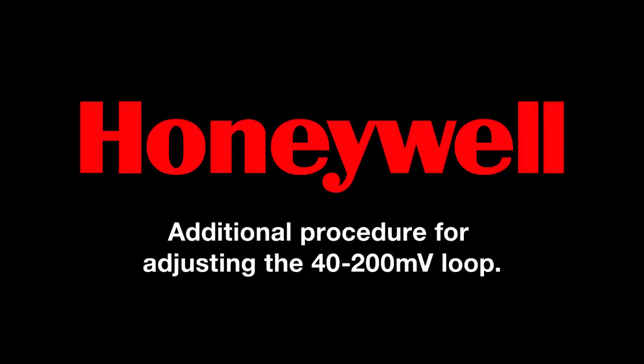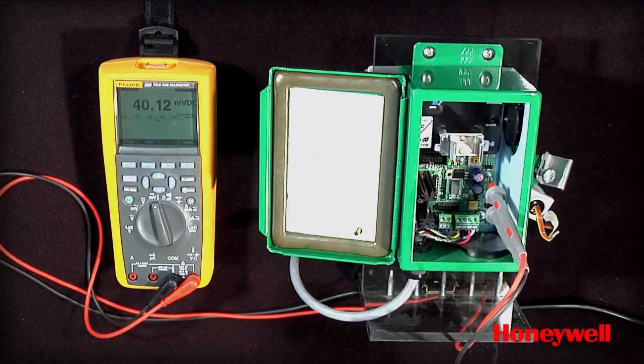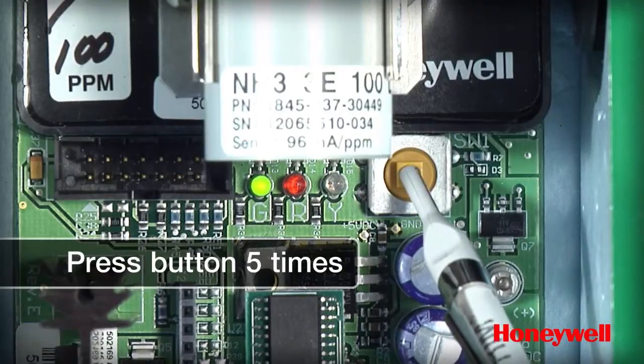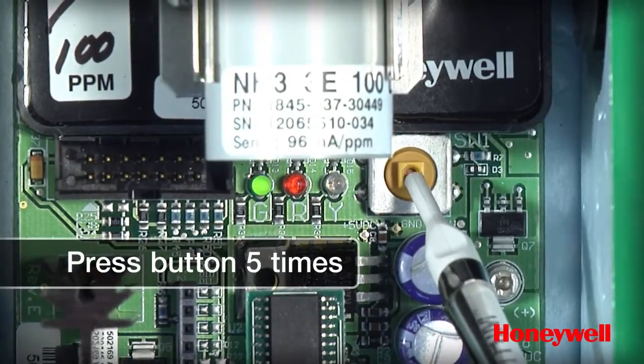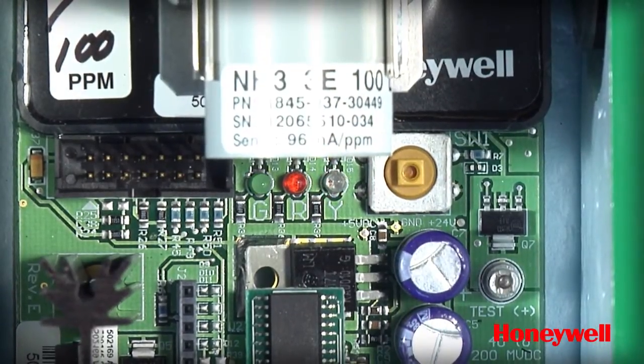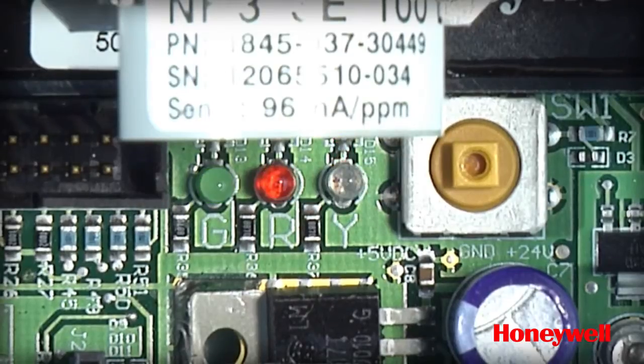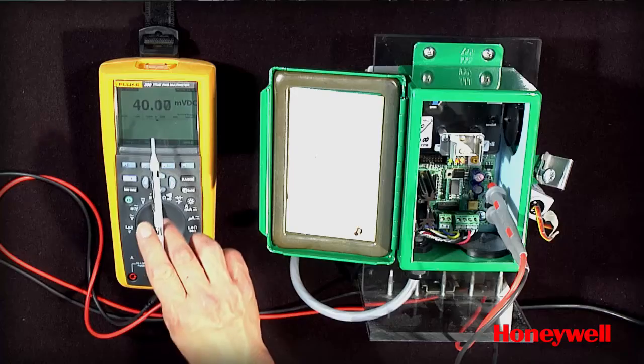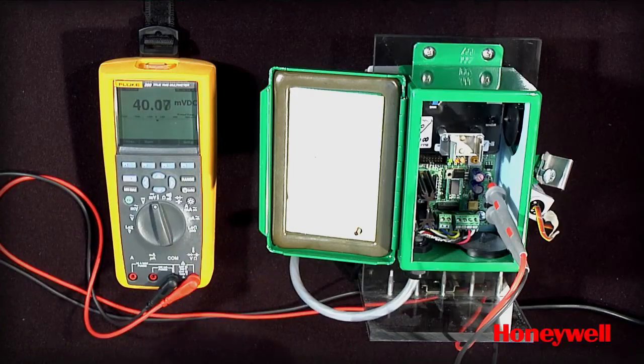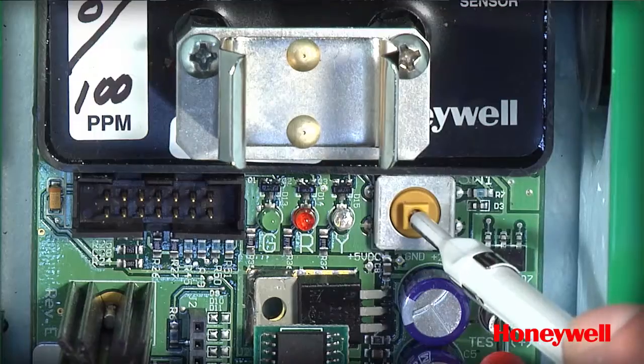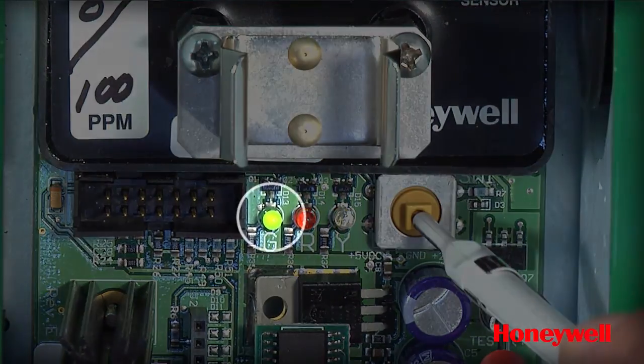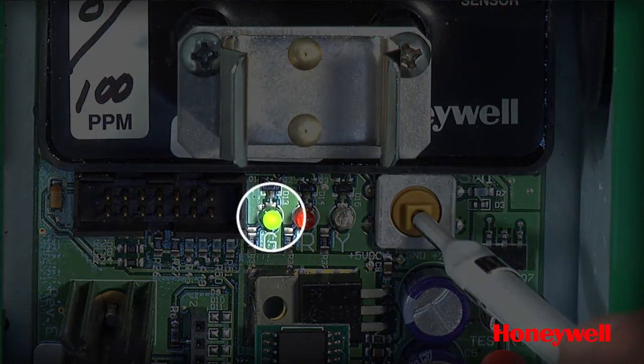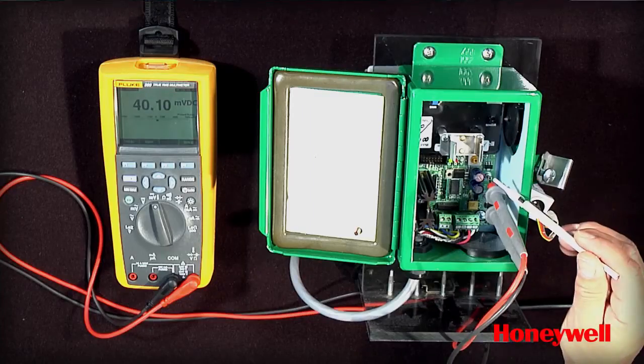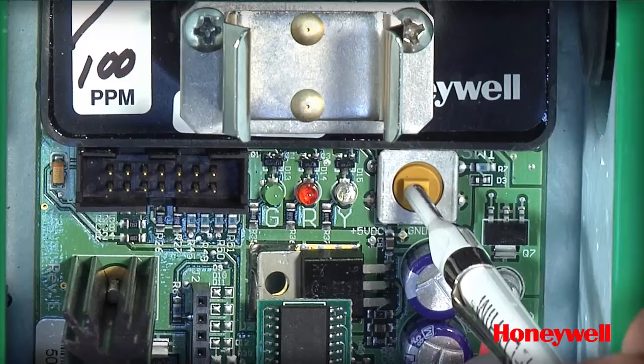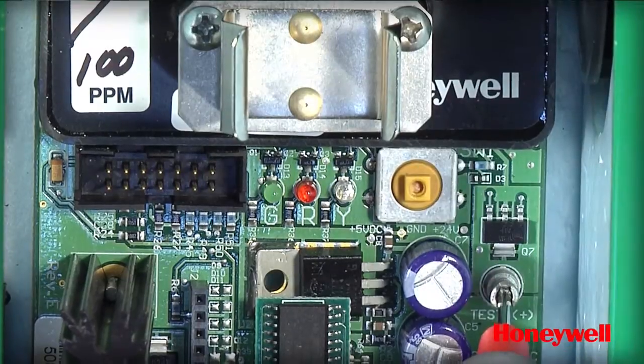If you need to do a 40 to 200 millivolt adjustment, you just press the button 5 times until all 3 LEDs blink simultaneously. This mode allows the operator to adjust the 40 to 200 millivolt loop to match your equipment of factory specifications. To exit this mode, press the button for about a second until the green LED is solid. Once the green LED is solid, you'll have to place the unit back into factory calibration mode by again pressing the button for 10 seconds.